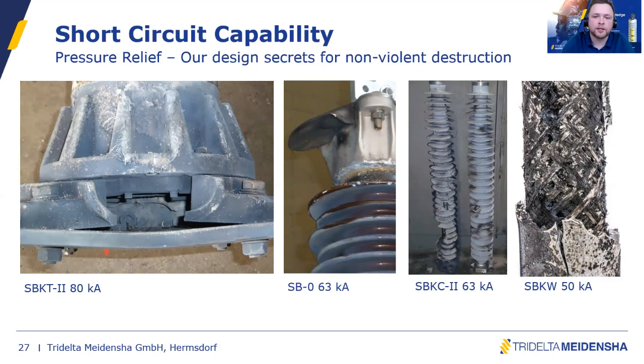Like you see in the middle, the SB0. We have the pressure relief device with a certain direction to the lower side of the surge arrester. So the air that is ejected will come out and have the perfect direction to meet the outcoming gas from the other side of the surge arrester, and it provides like a canal where the whole short circuit current can flow across the air. So the surge arrester protects itself by releasing the pressure and by creating a conductive path outside of the surge arrester.